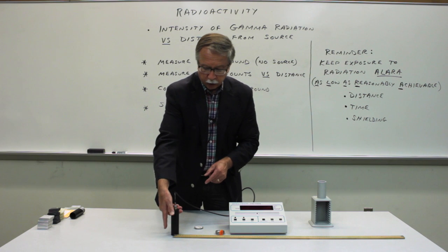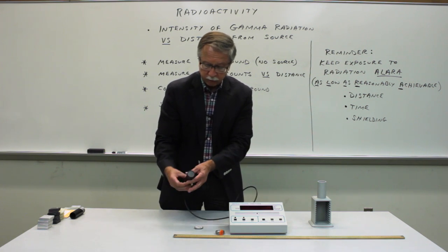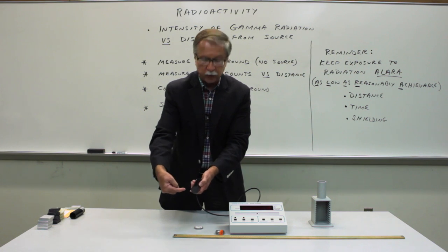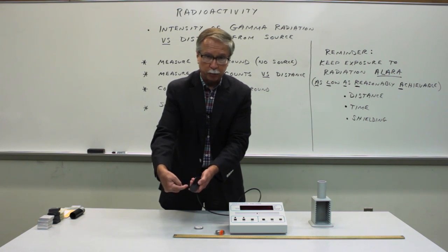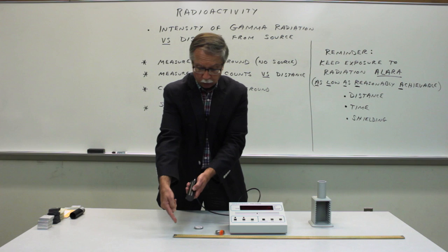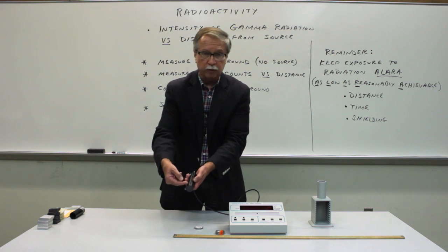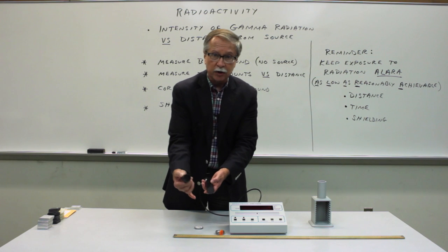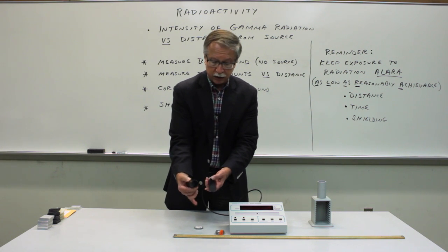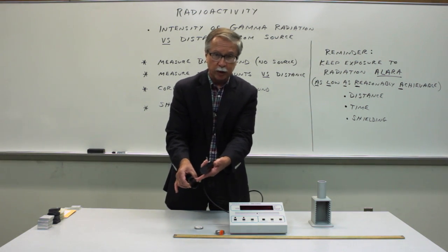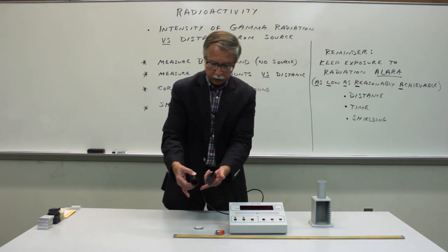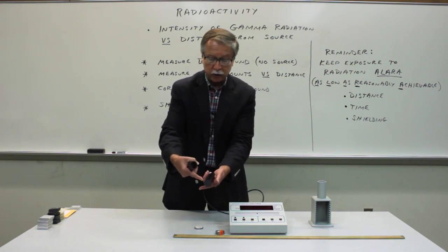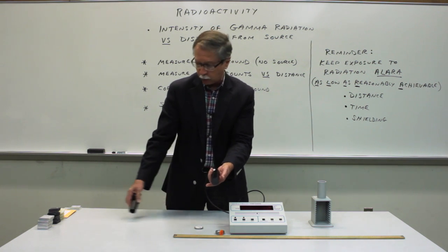Just a word of caution: these tubes have extremely fragile windows on the end. If you poke that window with a finger, a pen, or with the end of the meter stick, you can fracture the window and that will destroy the tube, as seen here with this one that's completely dead. What you see there is the bare wire inside the metal cylinder of the tube. So be careful not to fracture that window.